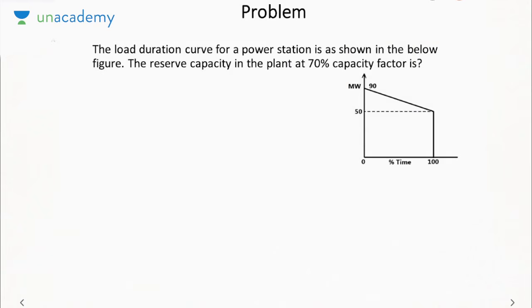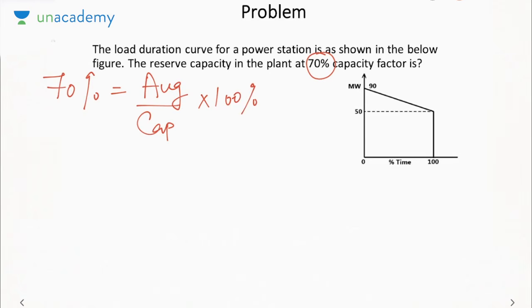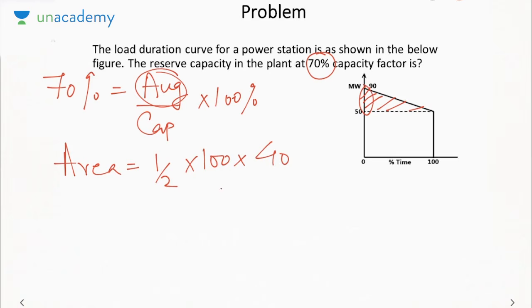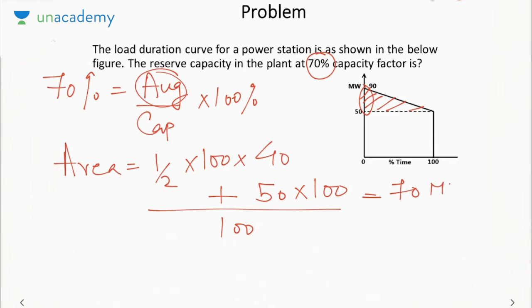In our next problem, it is saying the load duration curve is shown. Reserve capacity we need to find at 70% capacity factor. Again, 70% capacity factor is equal to average by capacity into 100%. So we do not know the average, but average can be determined from the load curve. So average is equal to area by duration. So area will be equal to the area of the triangle, half into width into height, where height is 90 minus 50, that is 40, plus the area of the rectangle, 50 into 100, divided by the duration. So it will be equal to 70 megawatt.